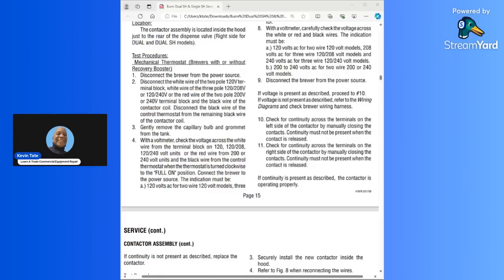Number 10. Check for continuity across the terminals on the left side of the contactor by manually closing the contacts. Continuity must not be present when the contact is released. 11. Check for continuity across the terminals on the right side of the contactor by manually closing the contacts. Continuity must not be present when the contact is released. If continuity is present as described, the contactor is operating properly.